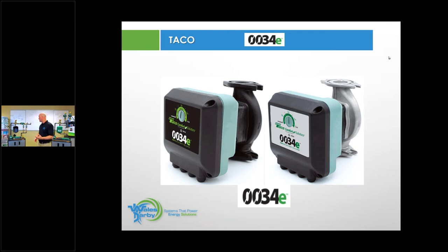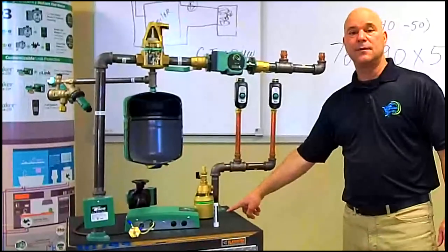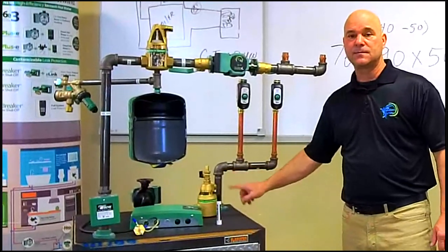So if I were to put a ΔT on here, my supply sensor would be here before my two zone takeoffs, and my return sensor would be here closest to entering the boiler, going back into the boiler after both of my zones come together and drop back down into the boiler.